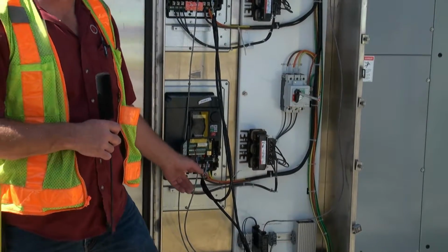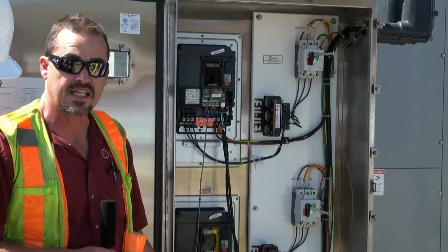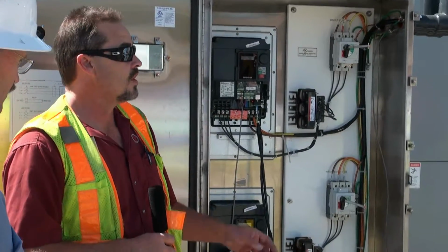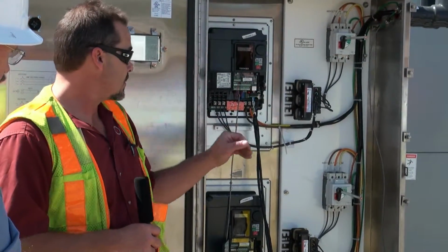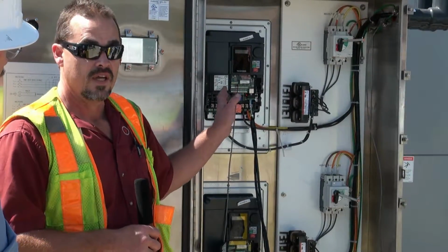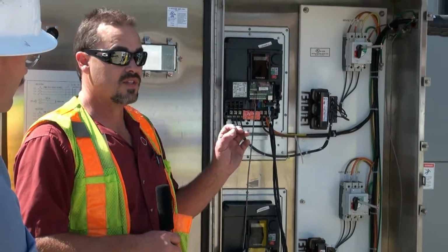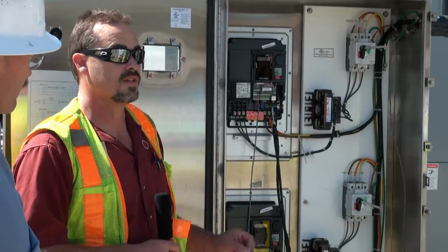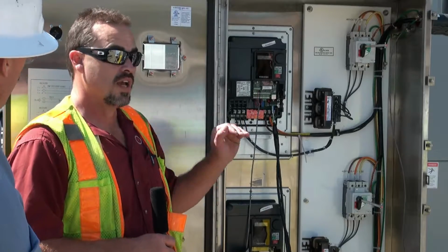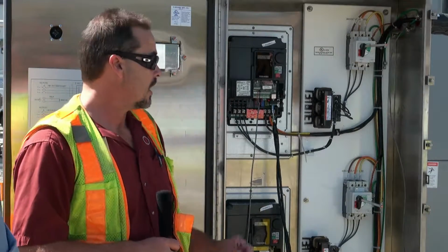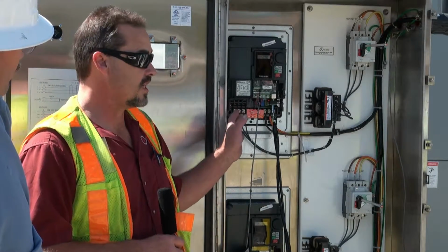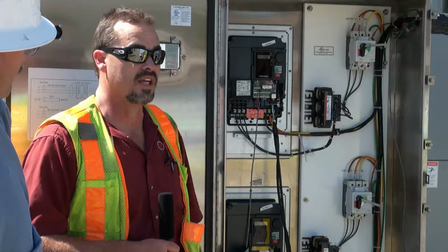And the way these drives are done is they're done with a PID. So it's checking the pressure and it's coming over here, and the drive has a set point, and you're setting the set point in your BMS system. So you can change the set point that way. Otherwise they do everything else on their own.